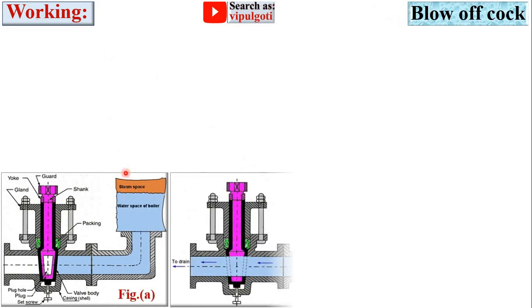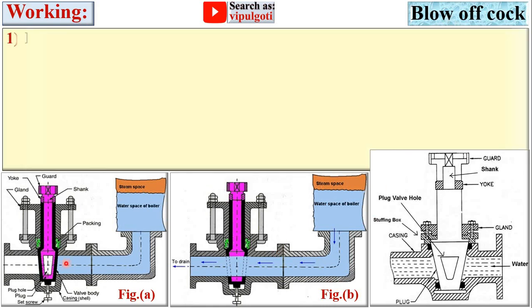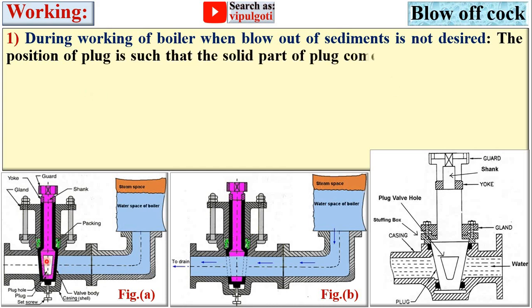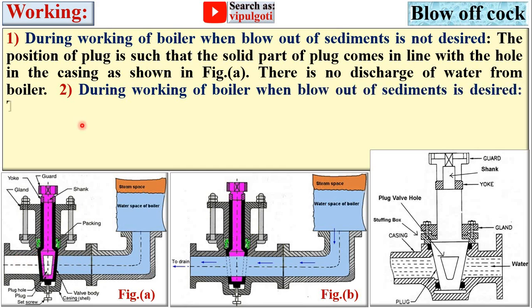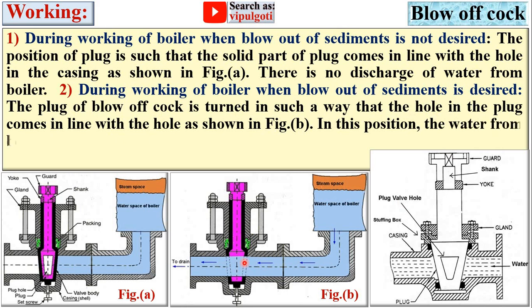Now the working of the blow-off cock. Consider figure A and figure B to understand the working. During working of the boiler, when blow-out of sediments is not desired, the position of the plug is such that the solid part of the plug comes in line with the hole in the casing, as shown in figure A. There is no discharge of water from the boiler. When blow-out of sediment is desired, the plug is turned such that the hole in the plug comes in line with the hole, as shown in figure B.